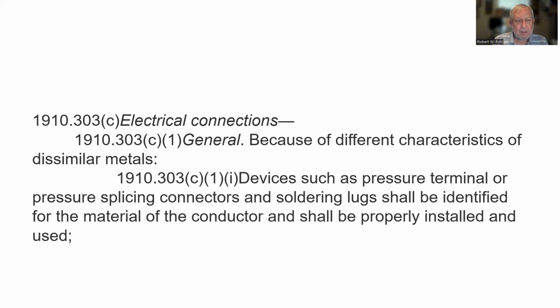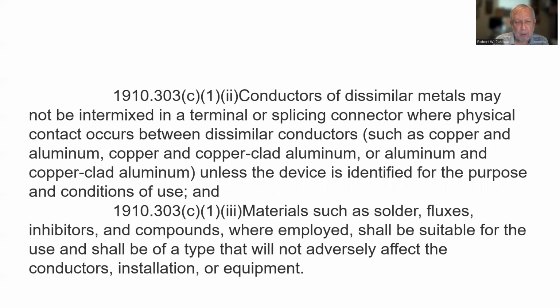Because of different characteristics of dissimilar metals, devices such as pressure terminal or pressure splicing connectors and soldering lugs shall be identified for the material of the conductor and shall be properly installed and used. Conductors of dissimilar metals may not be intermixed in a terminal or splicing connector where physical contact occurs between dissimilar conductors, such as copper and aluminum, copper and copper-clad aluminum, or aluminum and copper-clad aluminum, unless the device is identified for the purpose and condition of use. Materials such as solder, fluxes, inhibitors, and compounds, where employed, shall be suitable for the use and shall be of a type that will not adversely affect the conductors, installation, or equipment.